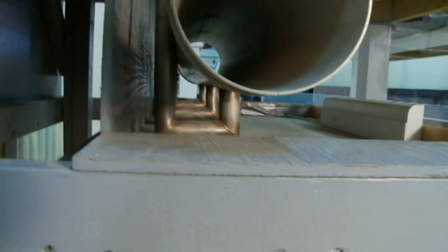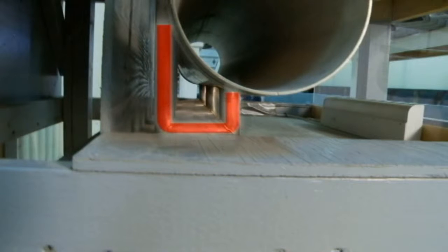The name J riser describes the shape of the pipe that takes air off the bottom of the header and introduces air to each underdrain lateral. If the air is not taken off the bottom of the air header pipe, water cannot exit the air header.